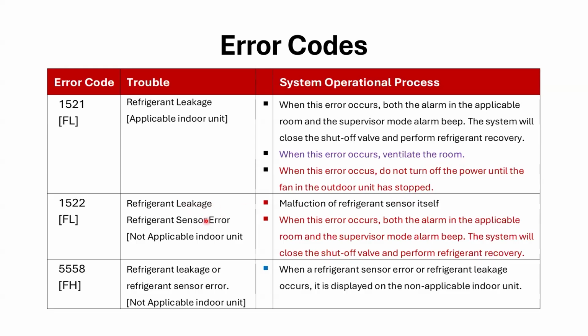1522, refrigerant leak, or refrigerant sensor error is what they're talking about here. So you would check that particular sensor and that particular unit. When this error occurs, both the alarm, same thing, the system will recover. So it does the same process there. And then 5558 here, refrigerant leakage or refrigerant sensor trouble. When a refrigerant sensor error or refrigerant leakage occurs, it is displayed on the non-applicable indoor unit. So those are your choices there on what you're going to see for error codes. I think that's the only 3 I remember seeing. That's pretty much what you're going to get.